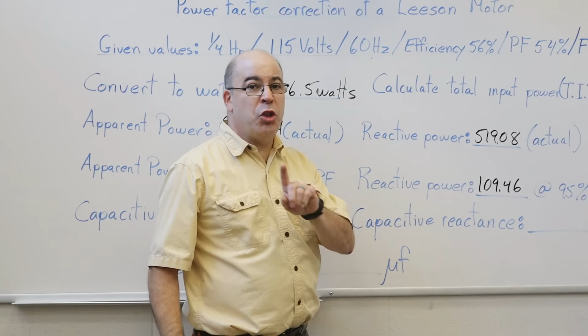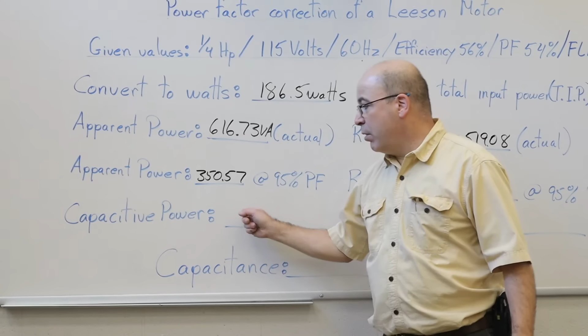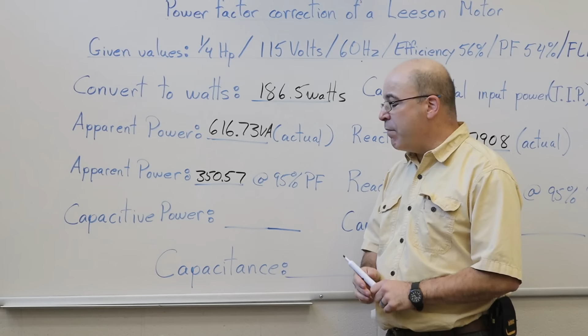This value represents the amount of reactive power we're going to allow the motor to draw from our circuit once we've done power factor correction. This is going to fluctuate, but it's basically 20% of the original value. Now we're going to calculate the amount of power we need to obtain from the capacitor, since we only have the one motor.